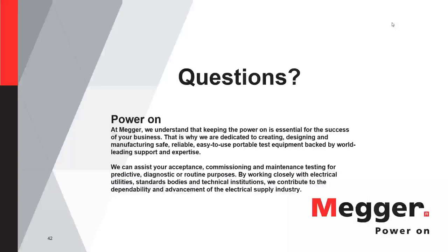I could add to this that in the practical application, you probably have to patch it together the best way you can. So you start using the arc reflection method, and you try to find if you have corroded neutrals at all. Not every unjacketed cable has the neutral corroded completely away. Last year I was on a cable in Arizona that was abandoned for a while already, but we got good results with the arc reflection method because there were still enough strands on the concentric left that were not corroded away to make the method work.